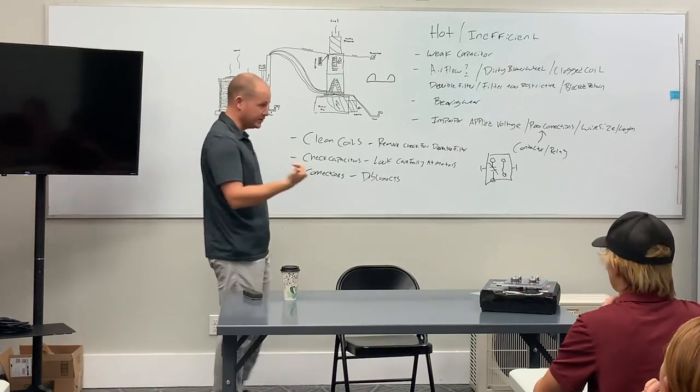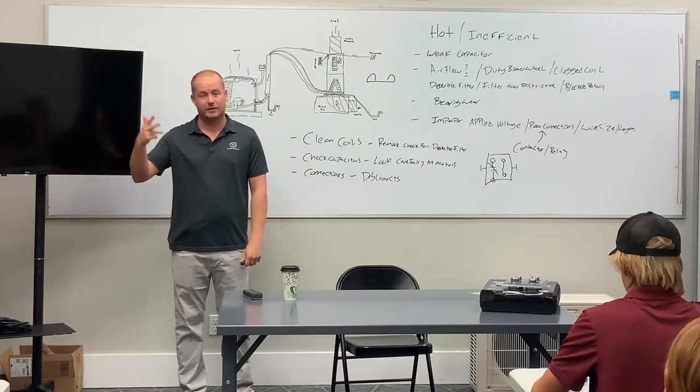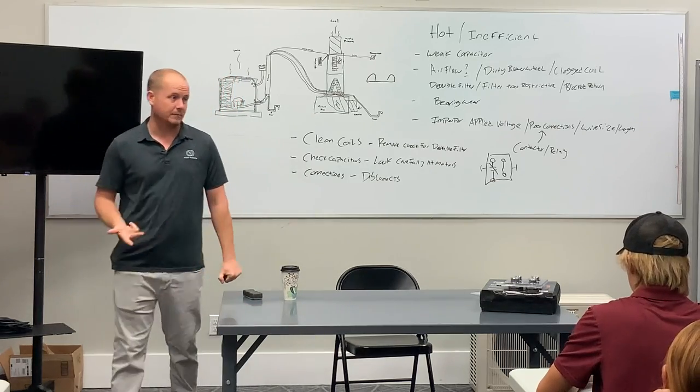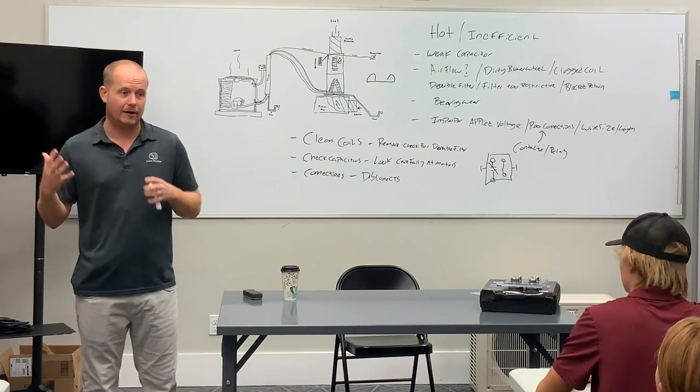Systems that don't have float switches, that's a big one. Float switches improperly wired, that's a big one. Float switches that aren't working, they're not shutting the system off, that's a big one. So that's another thing to be looking at regularly.